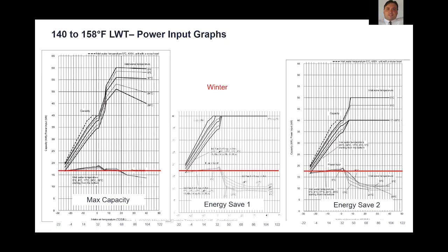And so you can see with winter operation, which is typically what you're critically sized for, especially in northern climates, all of these curves, regardless of the mode, in terms of capacity and power input pretty much converge below this roughly 32-degree mark. You can see the curve shapes all kind of line up there. It's really during these summer conditions where you have this trade-off of higher peak output capacity, depending on the mode, with a corresponding demand input penalty associated with that.